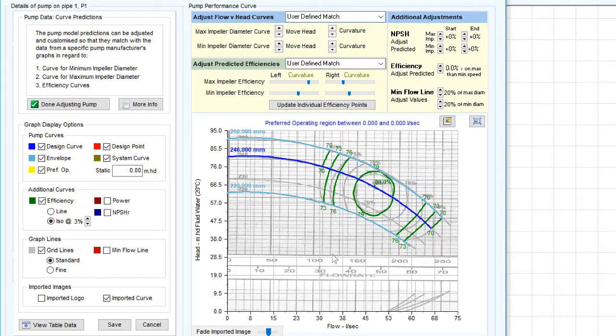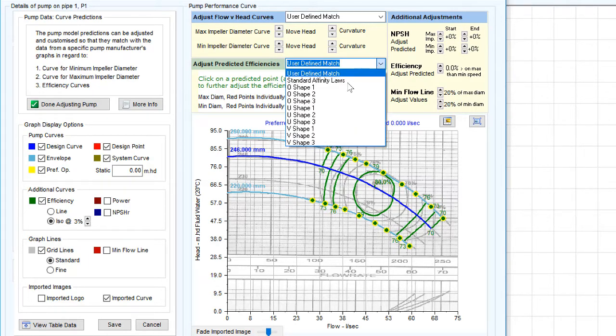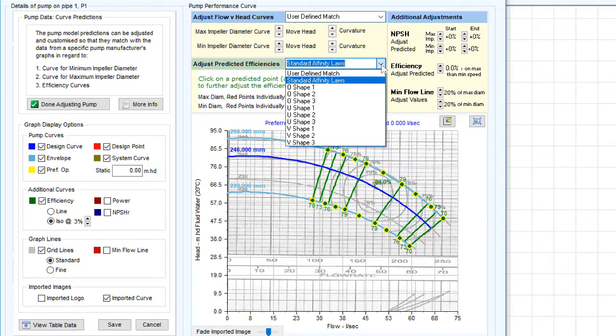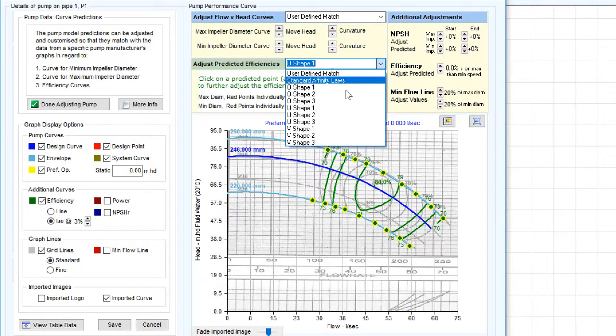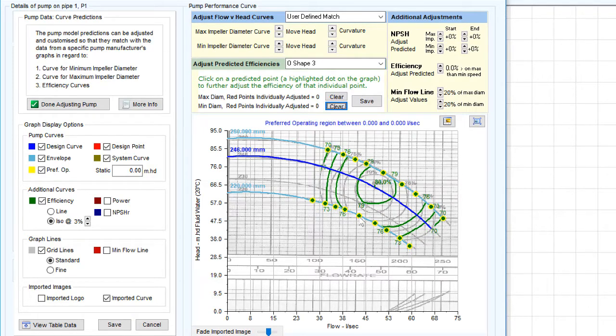These adjustments should be used to match the predicted efficiency curves to the efficiency data lines provided on the graph. We can now go on to update the individual efficiency points on the maximum and minimum performance curves by selecting the Update Individual Efficiency Points option. Alternatively, you can select a new initial starting position from a number of predefined ISO efficiency shapes in the drop-down options.